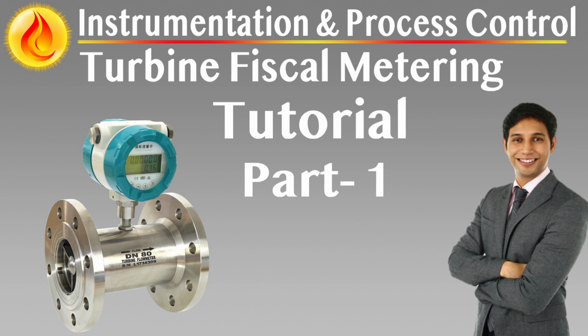Metering run architecture. Each parallel metering run is a fully self-contained measurement line, equipped with strainer, DP-monitored, flow straighteners, dual pickup turbine meters, pressure and temperature instrumentation, flow control valves, and leak check diverter valves. The dual pickup configuration allows for pulse verification integrity, a mandatory requirement under fiscal regimes. Metering runs are also equipped with thermal relief and isolation features, ensuring the system remains secure during shutdowns or proving transitions. By isolating metering lines, proving accuracy and redundancy are inherently supported.